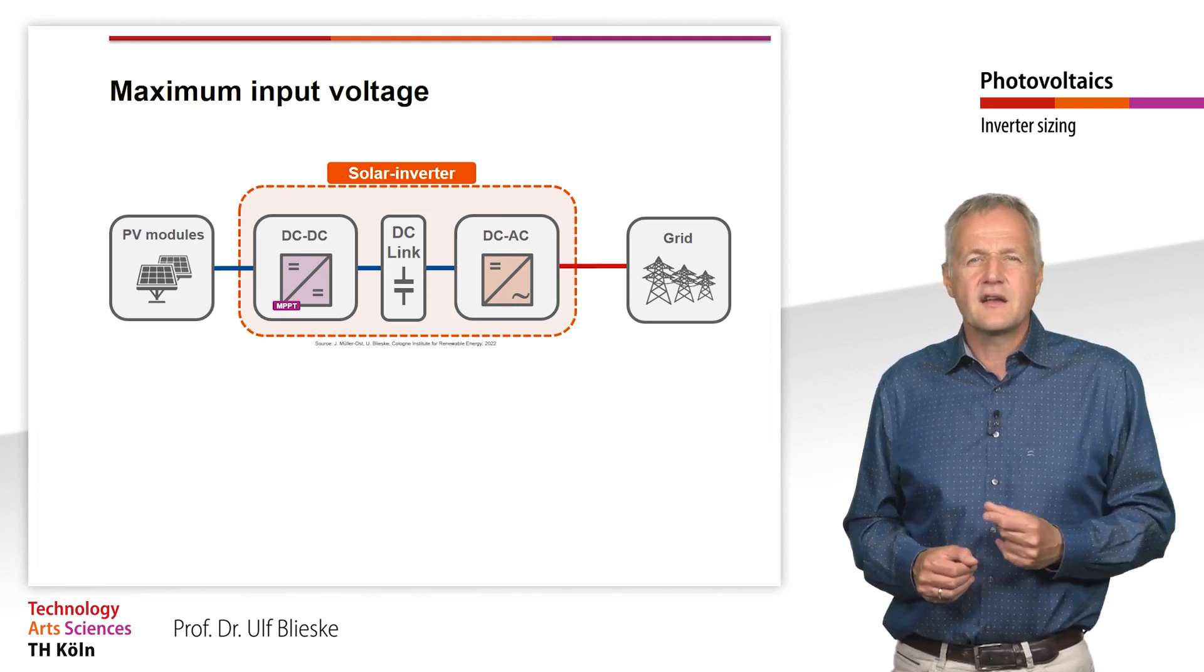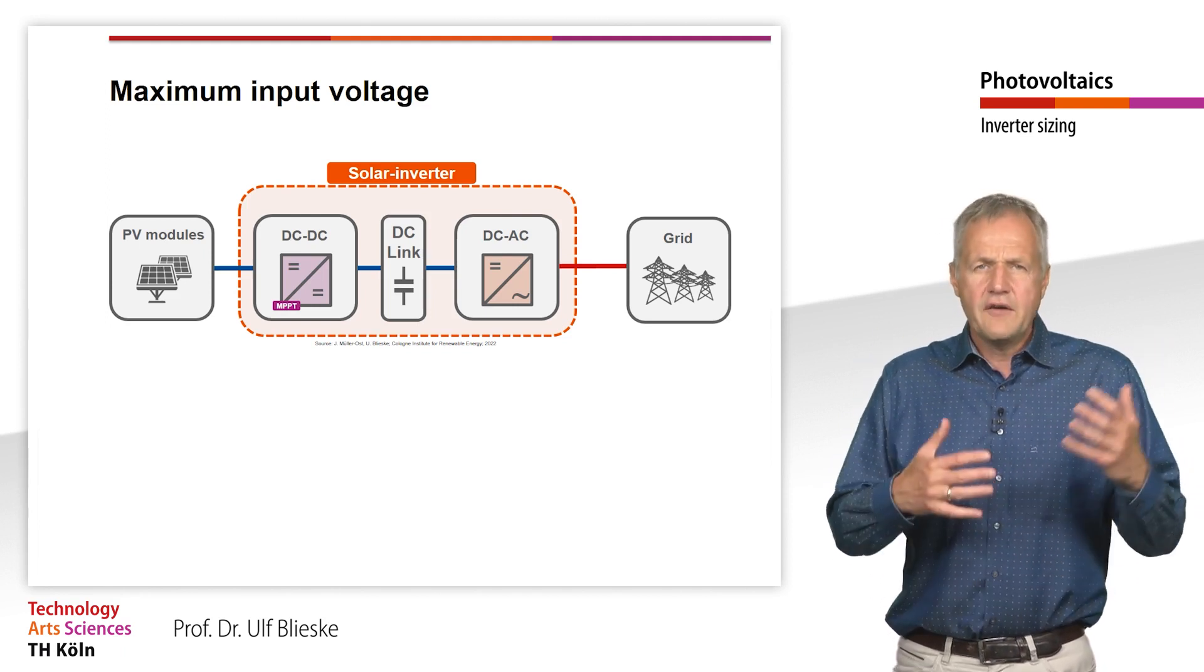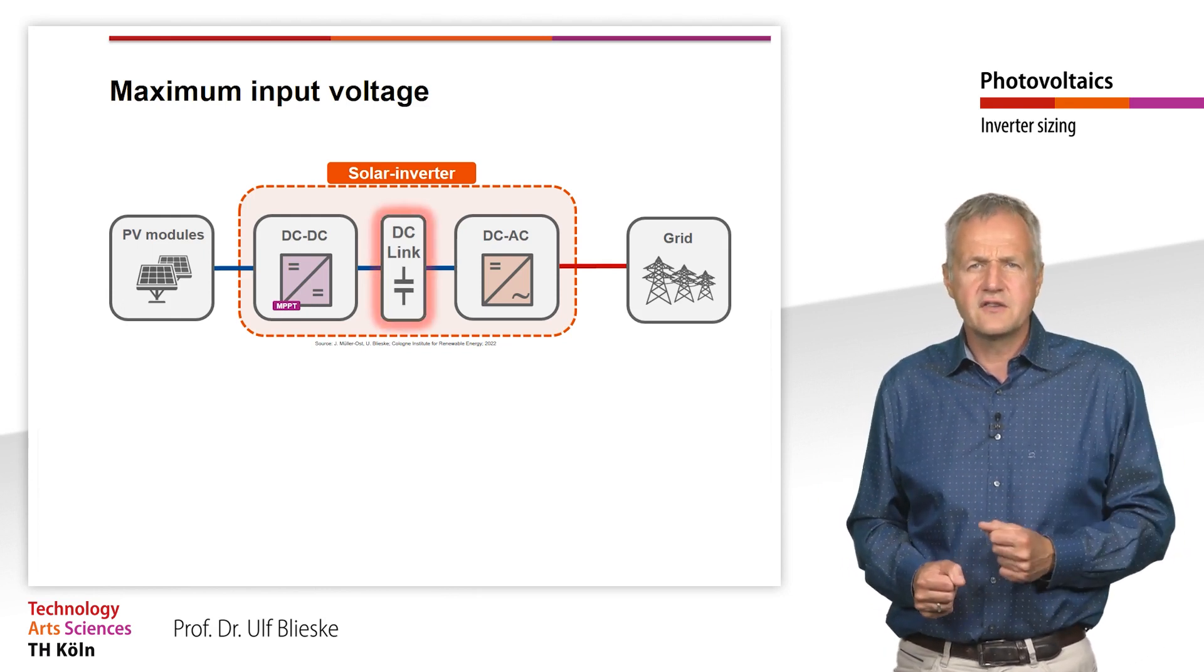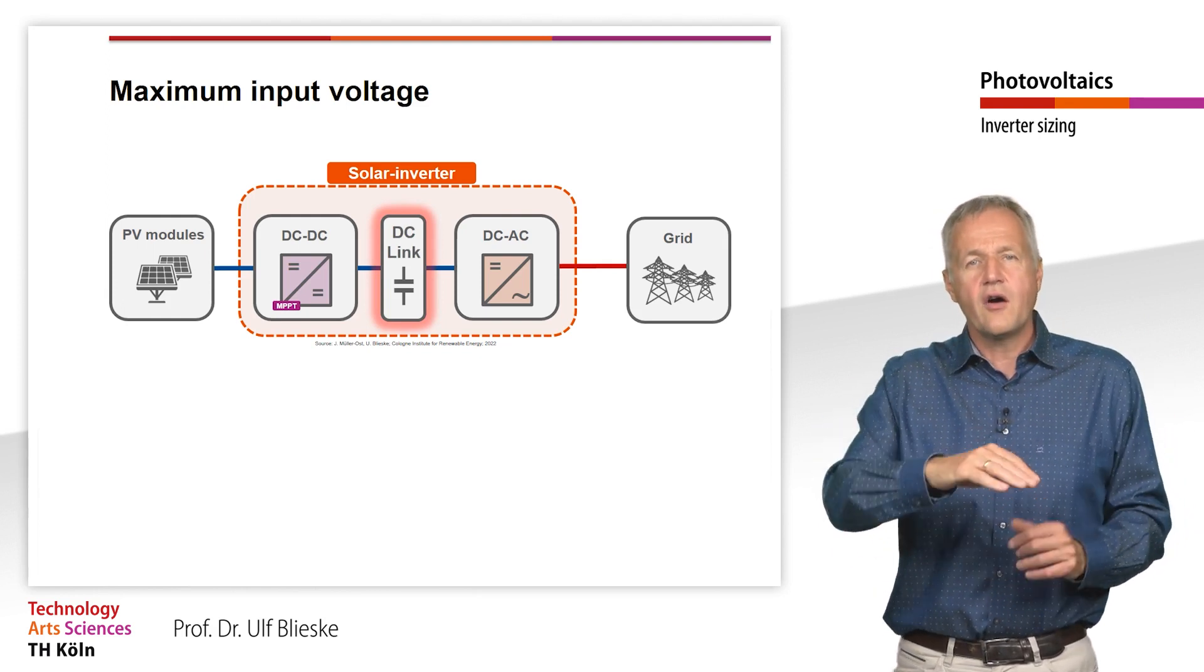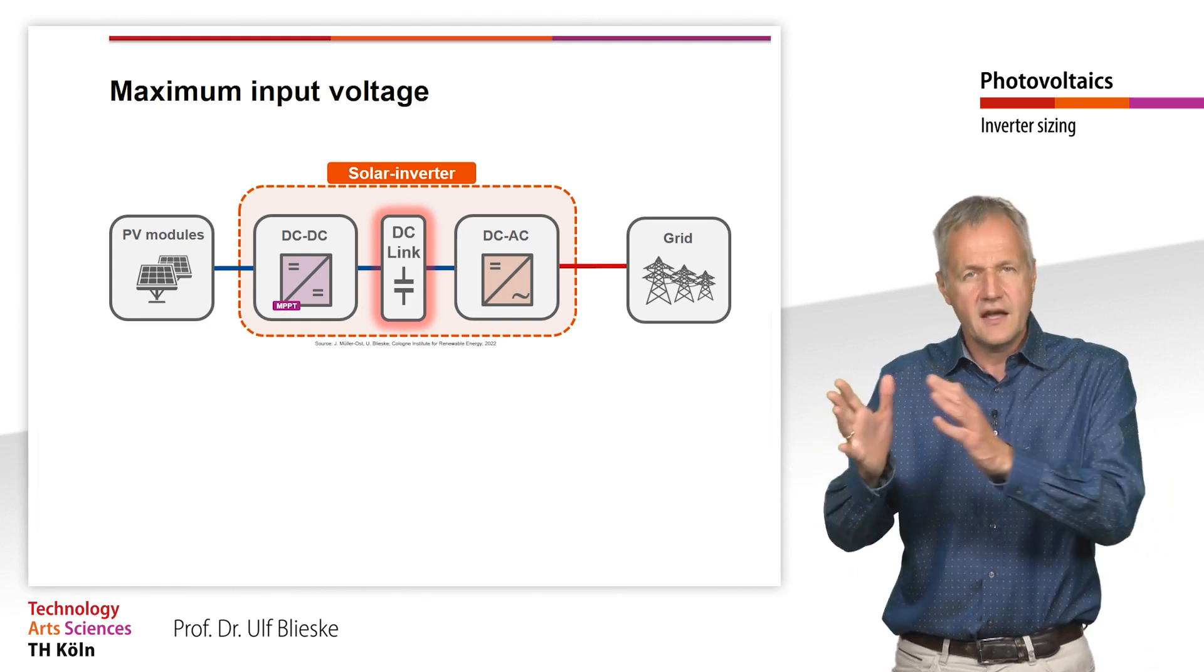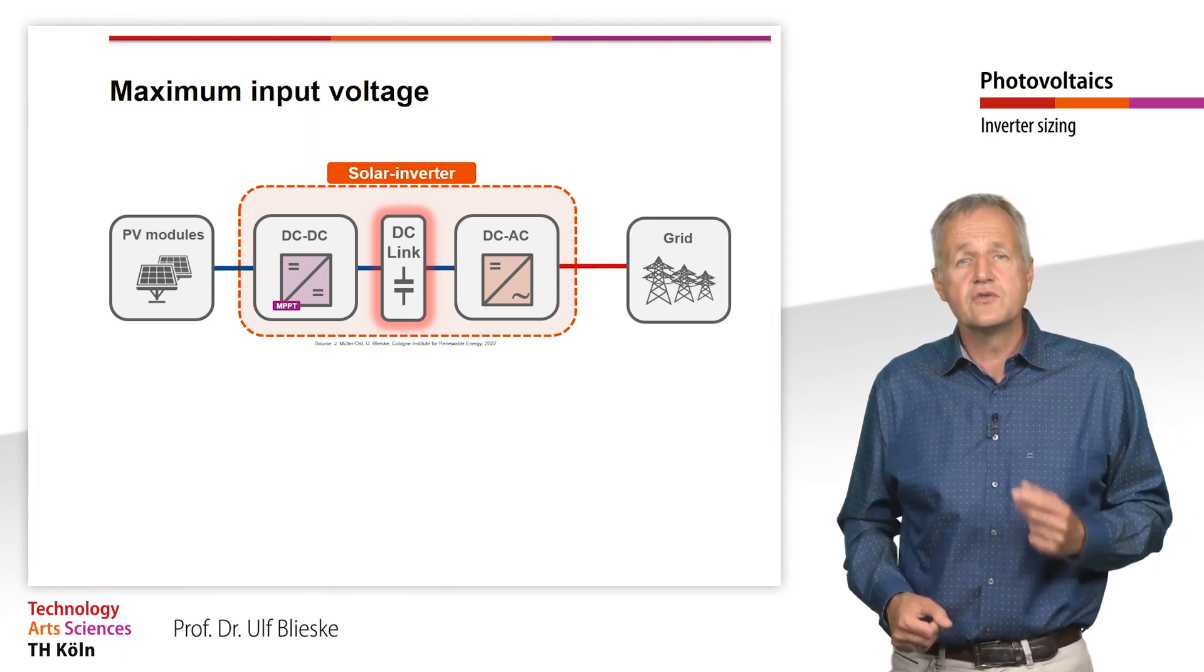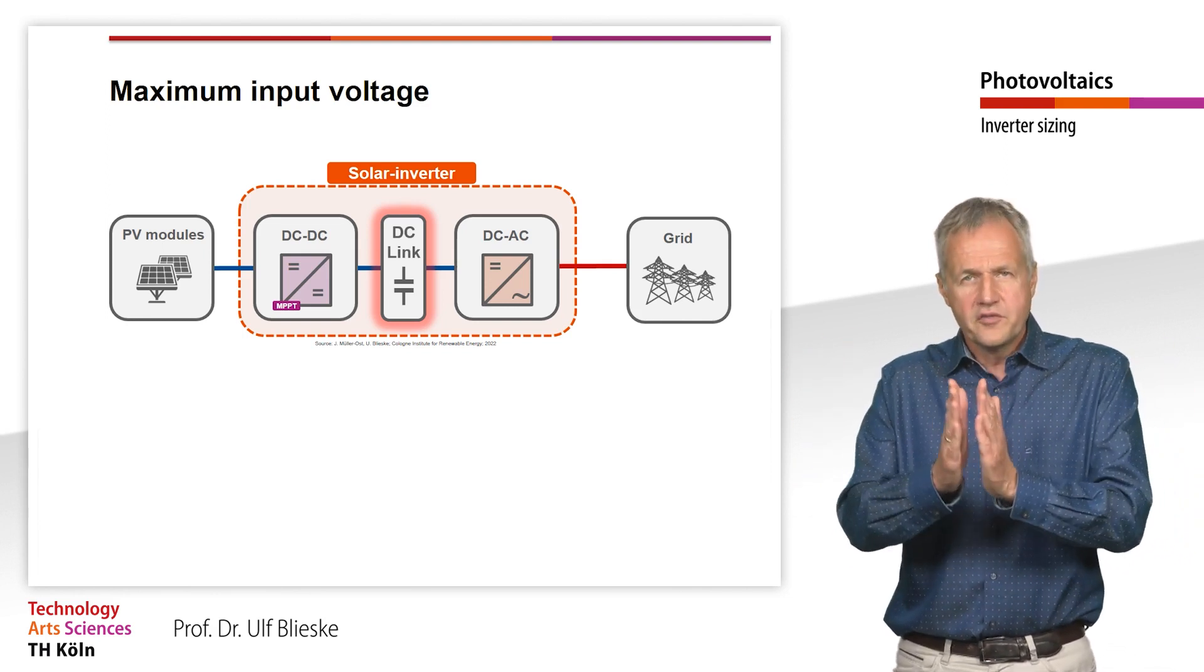Let us take another look at the schematic structure of an inverter. Every solar inverter has a large capacitor, the so-called DC link. This capacitor is the interface between the continuous energy flow of the solar generator and the alternating energy flow of the AC grid. Here, so-called electrolytic capacitors are usually used, which offer a large capacity on a very small space.